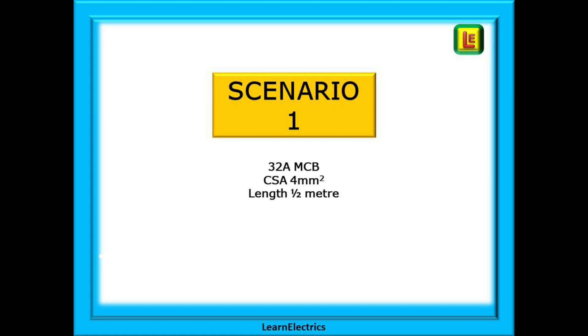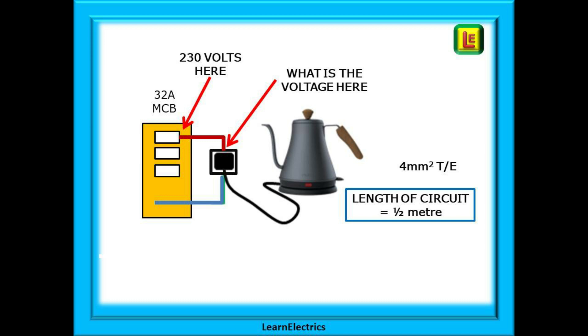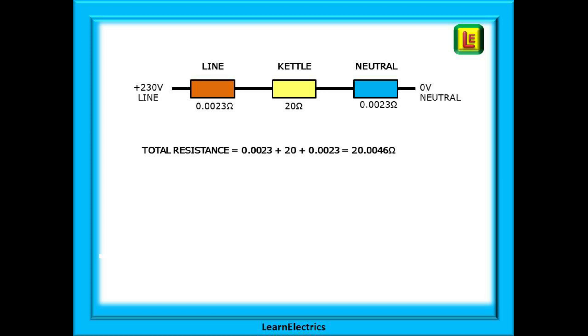Scenario one: a circuit protected by a 32-amp MCB with four-millimeter twin-and-earth cable. A socket is installed next to the consumer unit, just half a meter from it. The voltage at the consumer unit is fixed at 230 volts. We can simplify this circuit including the kettle and visualize it as three resistances in series: the line conductor at 0.0023 ohms (half a meter of four-millimeter copper cable), the kettle as a 20-ohm resistance, and the neutral conductor at the same value as the line.